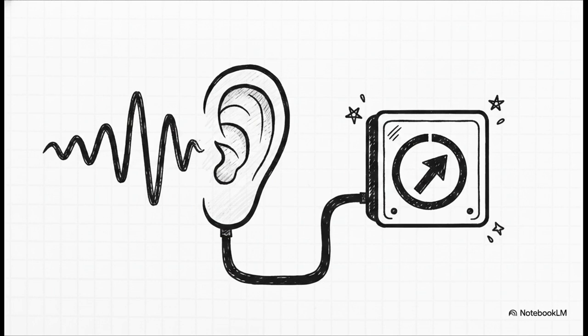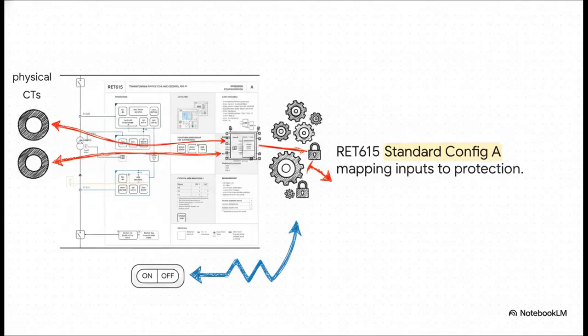It's exactly like a hearing aid. The relay literally adapts its hearing to whatever environment it's placed in. Whether it's being fed by a 2000 to 5 CT or a 2000 to 1 CT, you just toggle a dial in the software. You get to reuse the exact same physical device across completely different projects. That is a massive cost and stocking advantage, because you aren't warehousing a bunch of different spare parts for every single CT rating in your facility. And once that software hearing aid is tuned properly, the data path is incredibly direct.